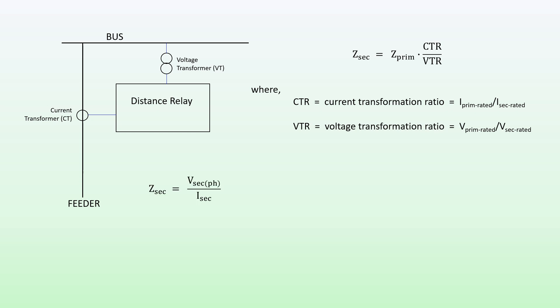The secondary impedance is really the secondary phase voltage divided by the secondary current. The secondary phase voltage is the voltage on the secondary side of the VT presented to the relay, and the secondary current is the current on the secondary side of the CT which is presented to our distance relay. The secondary voltage is our primary phase voltage divided by the VT ratio.